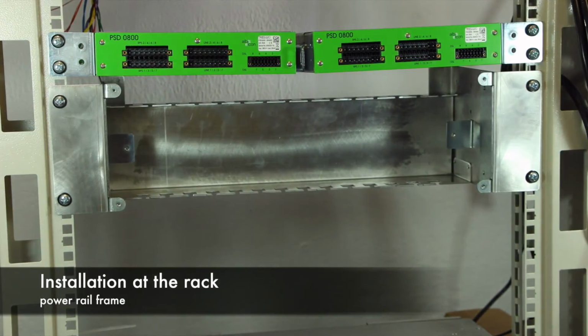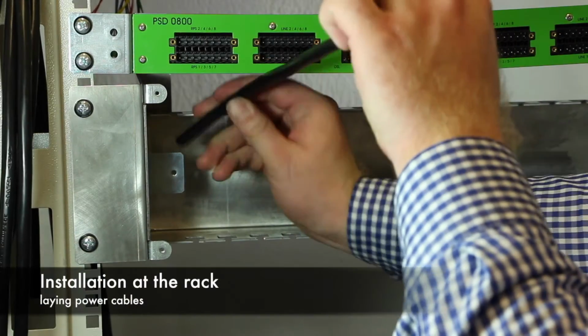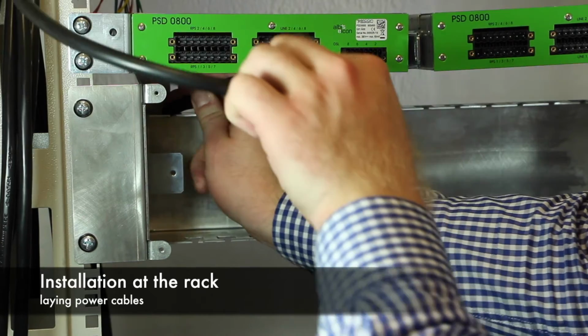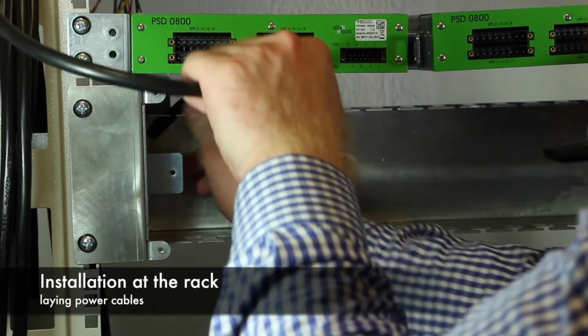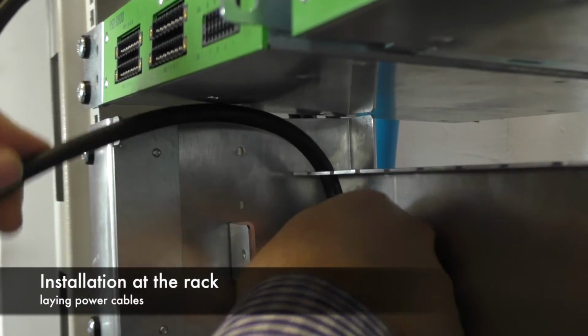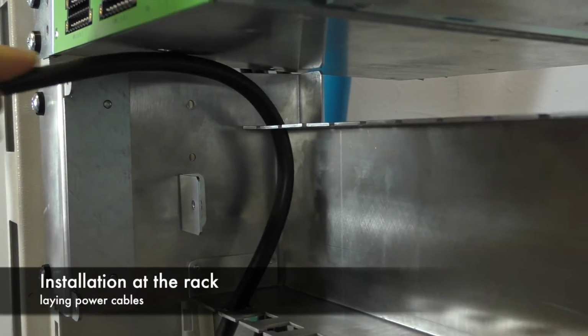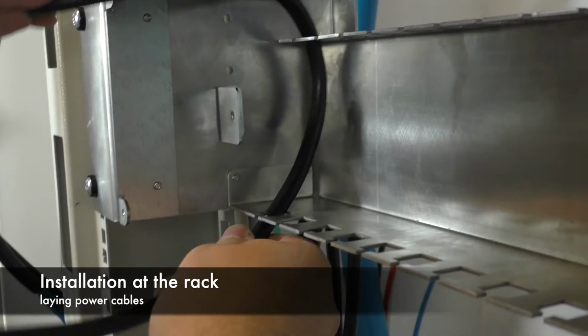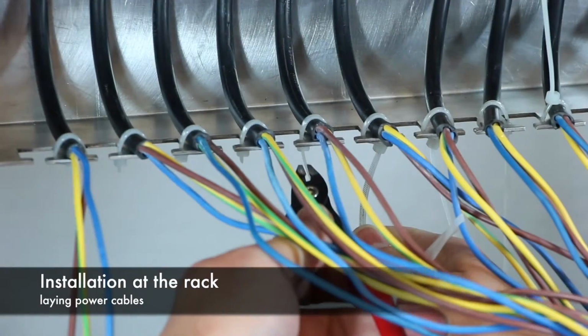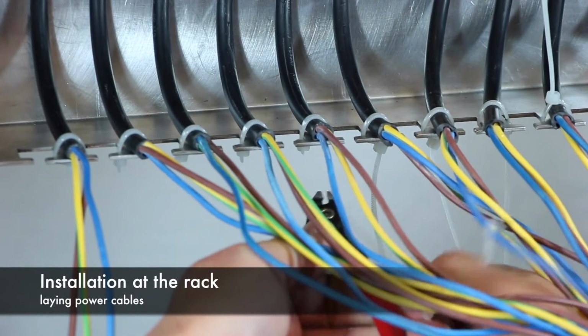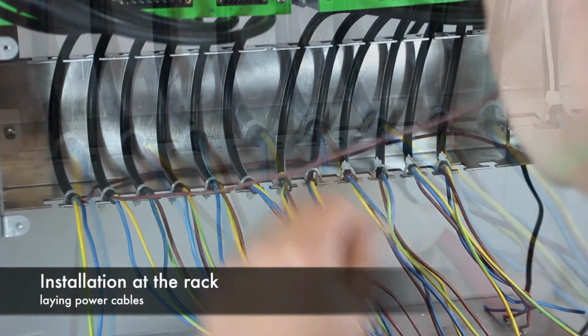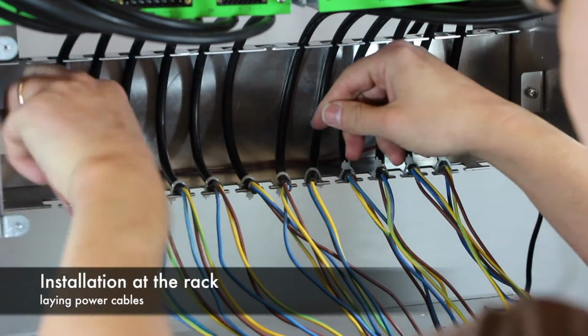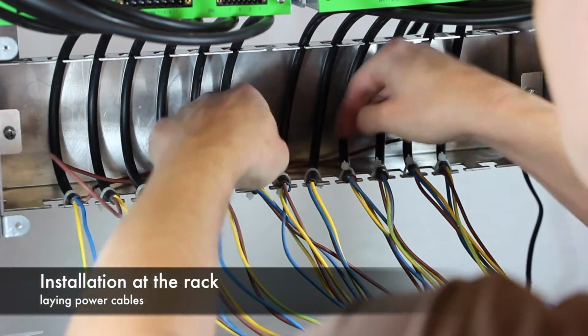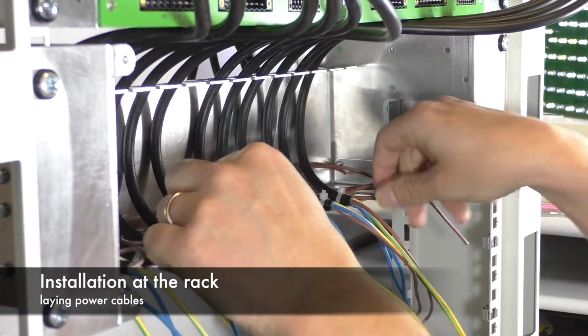Now we prepare the wiring of the power rail. Take the power cables from the left or the right of the power rail frame and thread them through the top recess of the cable guide. Place the power cables on the lower leg of the cable guide. Strip 400 mm of each cable and secure the cables at the edge of the insulation using the cable ties. Please make sure that the power cables remain close to the cable guide. The brown cable core is fed through to the right along the cable guide.